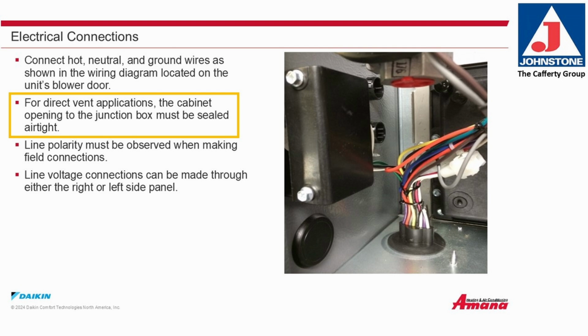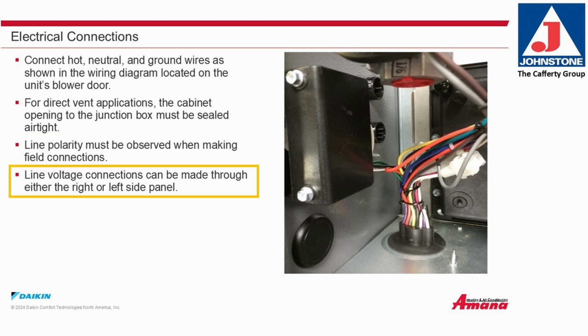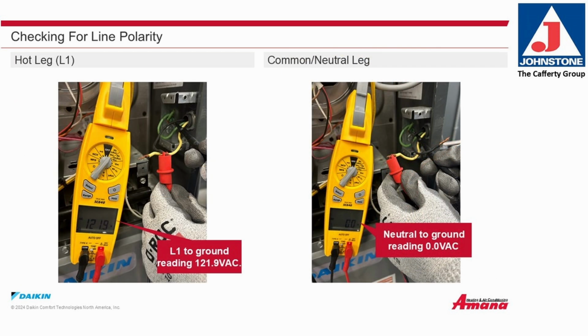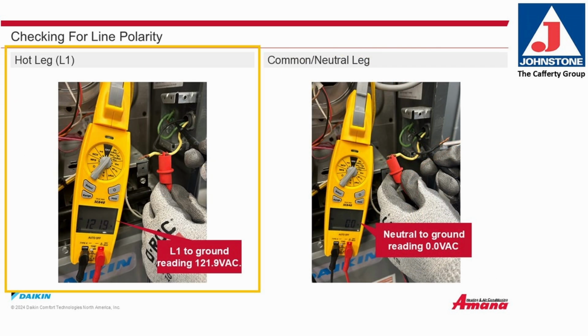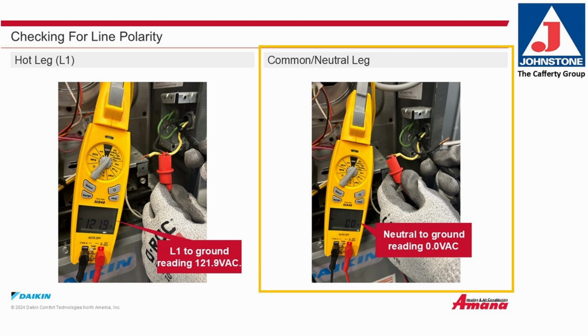Connect hot, neutral, and ground wires as shown in the wiring diagram located on the unit's blower door. For direct vent applications, the cabinet opening to the junction box must be sealed airtight. Line polarity must be observed when making field connections. Line voltage connections can be made through either the right or left side panel. Checking for line polarity. The hot leg L1 to ground reading should be around 120 volts AC. The common or neutral wire to ground should be 0 volts AC.